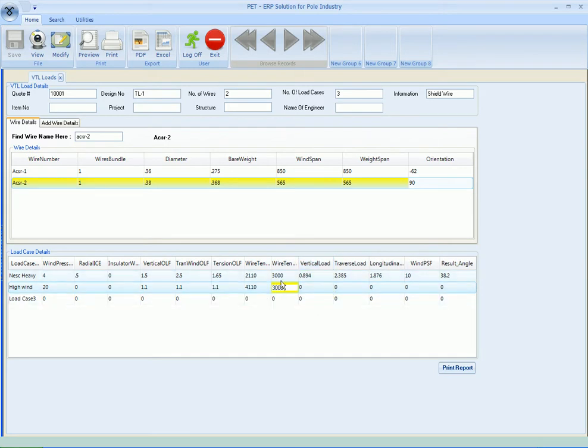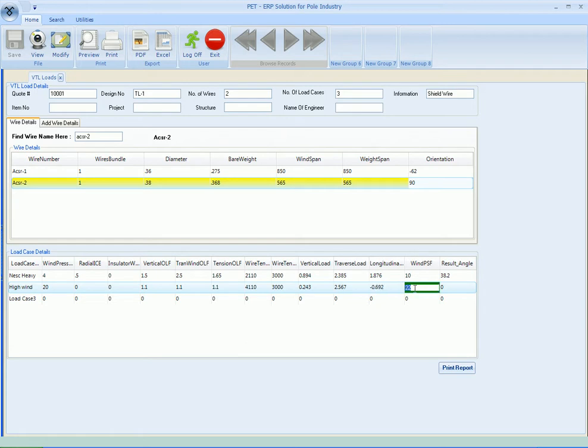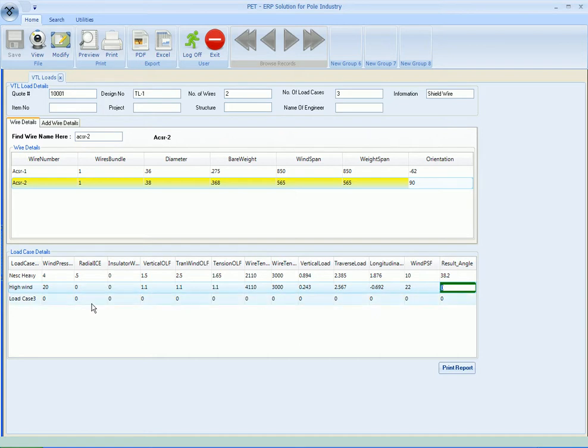And wire tension suppose it's 4110 for the first wire, and for the second wire it is again 3000. Okay, vertical load is 0.243 kips, transverse load is 2.567 kips, the longitudinal is minus 0.692 kips, wind PSF is 22, and resultant angle is 0. So we'll repeat the procedure for each load case.